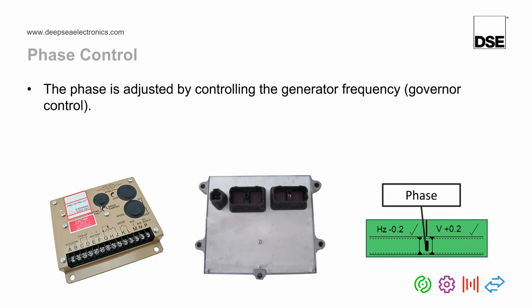So as the phase control is done by slightly changing the generator's frequency, this means we must be using the governor again, because we are changing frequency to affect phase. So again, phase control is done by using a governor such as this GAC here on the left, the engine's ECU in the middle, and on the synchroscope, the phase is shown by the dot that appears on the screen.